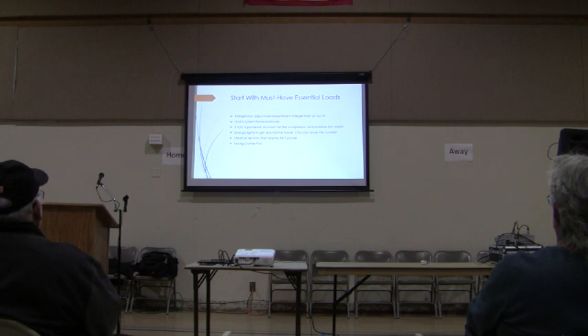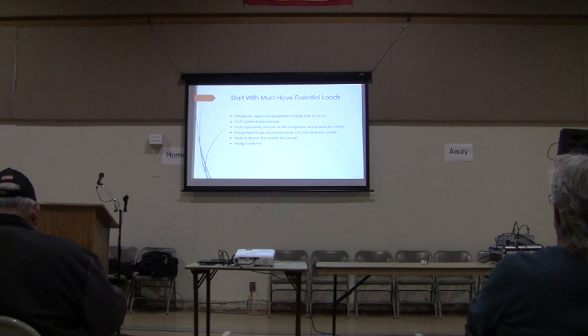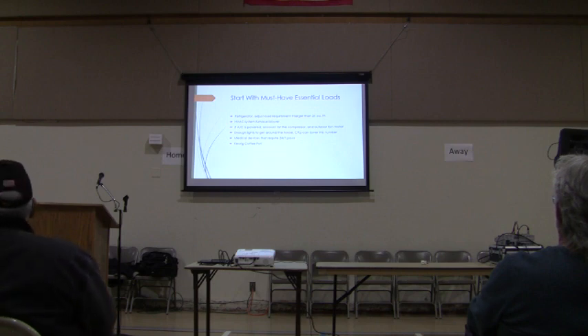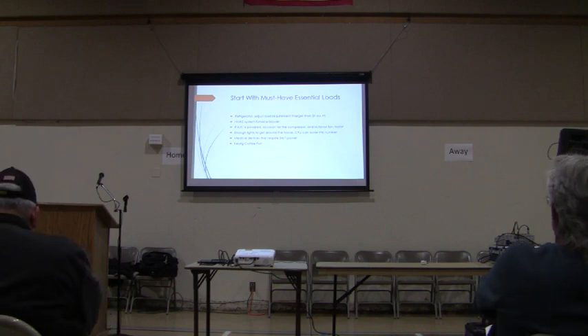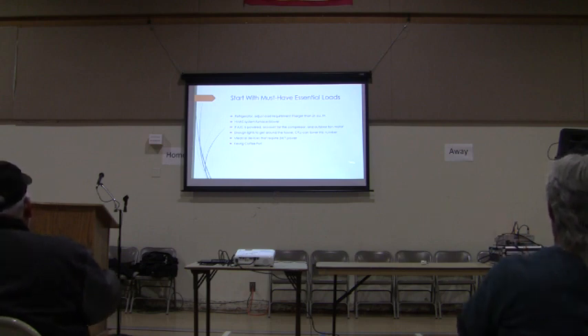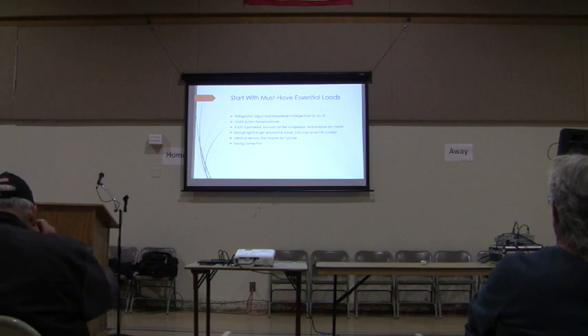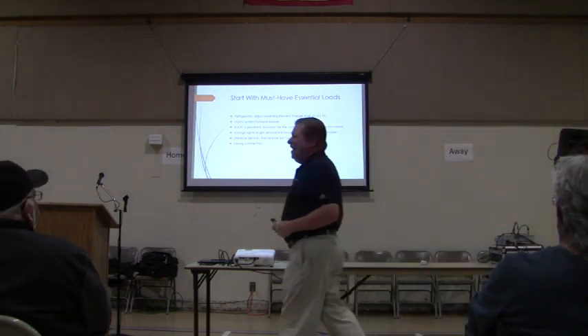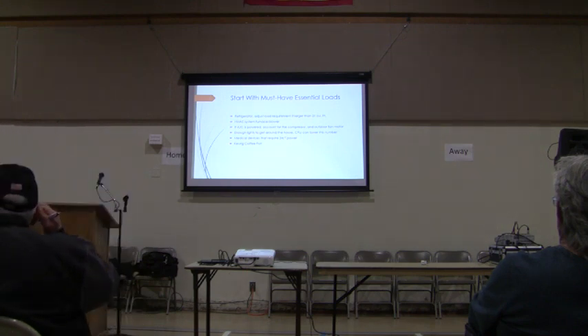Your HVAC system furnace blower motor is typically around half horsepower, and that will probably be your biggest load unless you pick your air conditioner as one of your essential loads - then you have to account for the compressor and outdoor fan motor. Enough lights to get around the house, CFLs will help lower that number. If you've got 20 60-watt light bulbs, you're talking 1,200 watts right there.